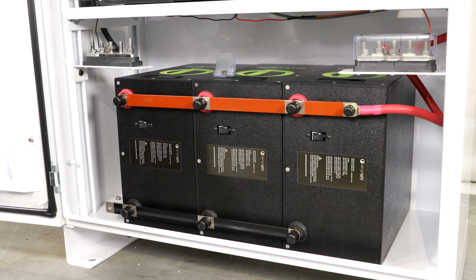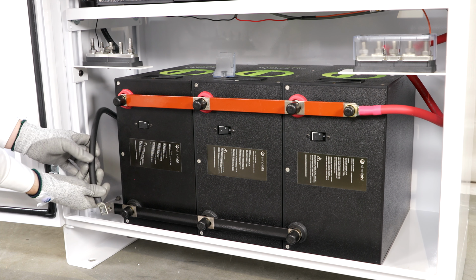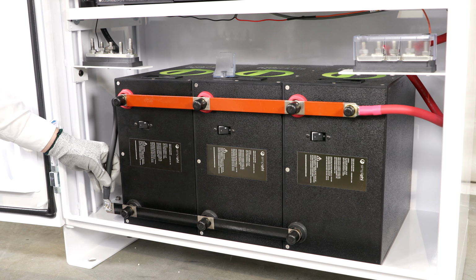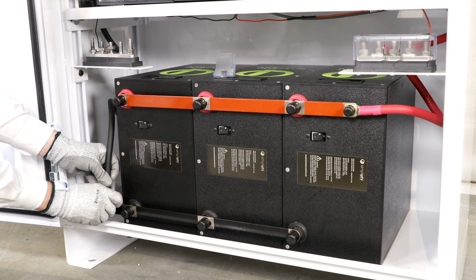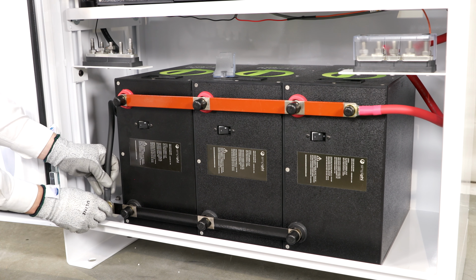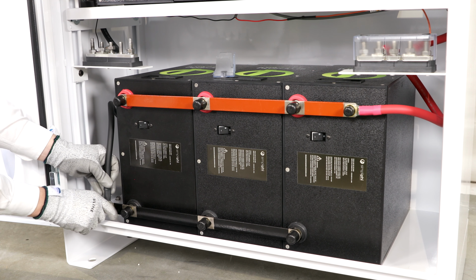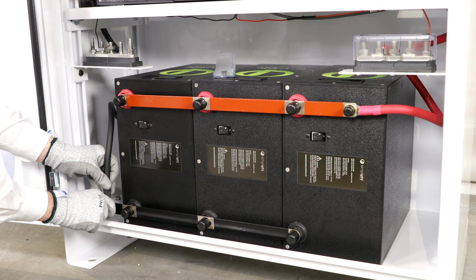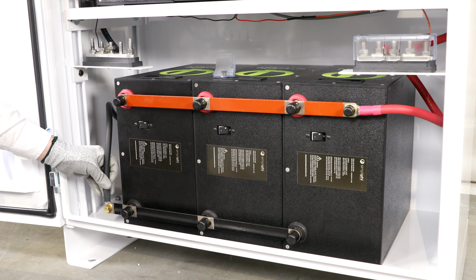When connecting the brass hex head cap screw, ensure the lock washer is placed over the screw's threading first, followed by the flat brass washer. Attach the cable at a 90-degree angle when securing it to the bus bar. Angle the cable so it extends directly up towards the 5-point terminal block. This allows the cabling to be routed more easily.